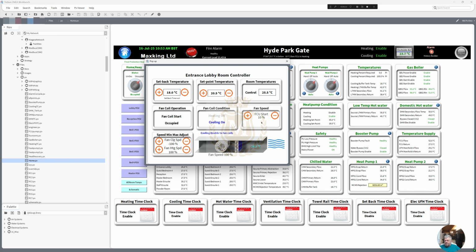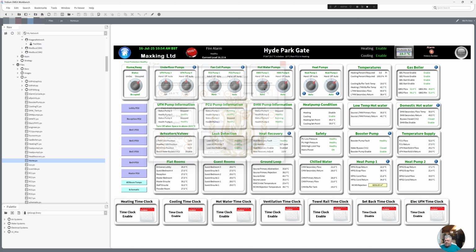And then this is just an adjustment that says that once the PI loop reaches 10% or above, we start the fan coil. So that's all this is for, the fan speed. We're naturally occupied and we're starting the fan coil. The setback temperature, if the setback time clock is on, which is currently disabled down here, we'll set it back further to 18 degrees at night time. But that is that one, and then it's the same for all the other fan coils.